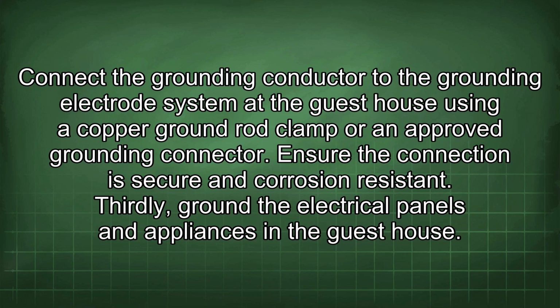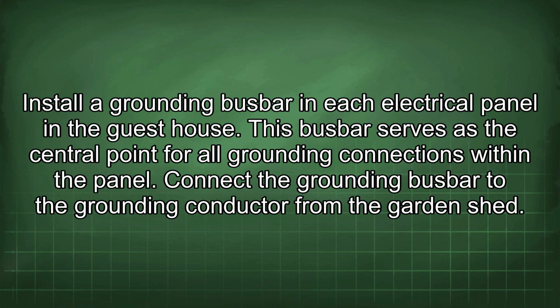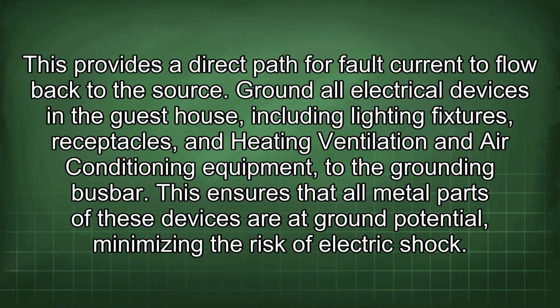Thirdly, ground the electrical panels and appliances in the guest house. Install the grounding busbar in each electrical panel in the guest house. This busbar serves as the central point for all grounding connections within the panel. Connect the grounding busbar to the grounding conductor from the garden shed. This provides a direct path for fault current to flow back to the source. Ground all electrical devices in the guest house, including lighting fixtures, receptacles, and heating, ventilation, and air conditioning equipment, to the grounding busbar. This ensures that all metal parts of these devices are at ground potential, minimizing the risk of electric shock.